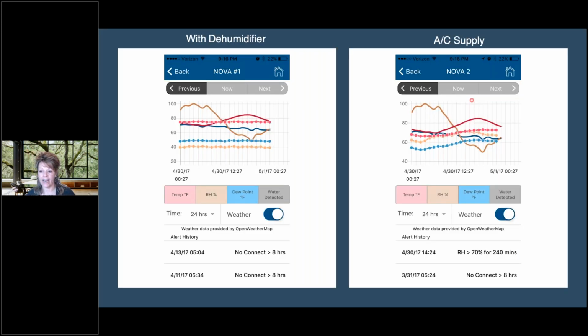We actually did a study on 2 Habitat houses in Northern Virginia, right next to each other on the same lot, built to the same energy standard, with the exact same footprints and blueprints. In one of them we used a dehumidifier and in the other we just used the AC supply. What you can see here is the dotted orange line is the RH. Now, they had to do some mold remediation before they actually closed up these crawl spaces, and so we were trying to really keep that crawl space dry down there. So it was set a little bit too low at first.